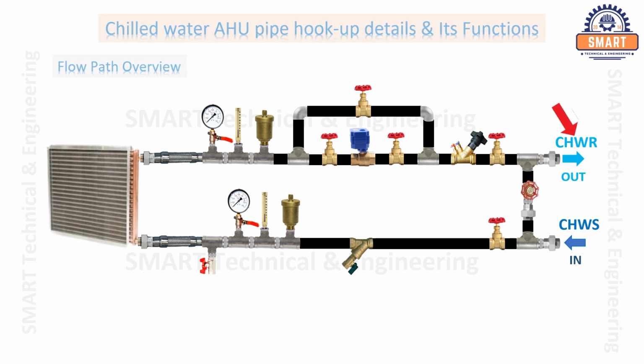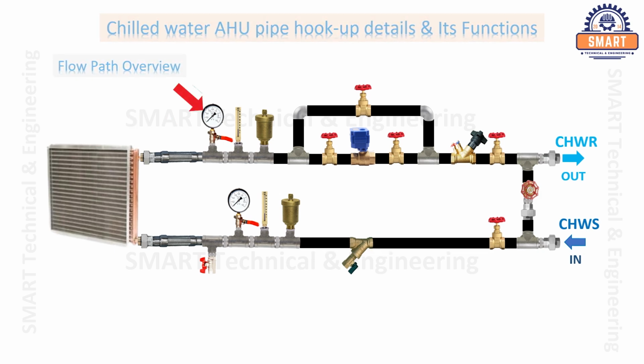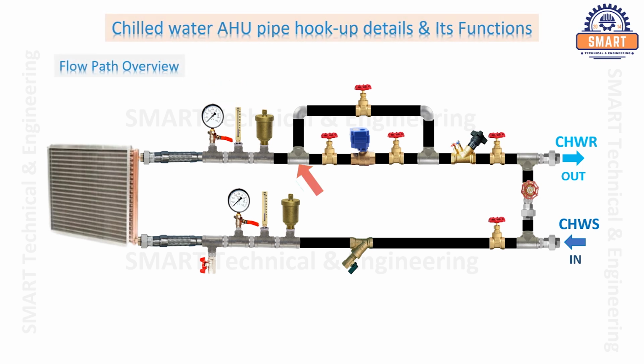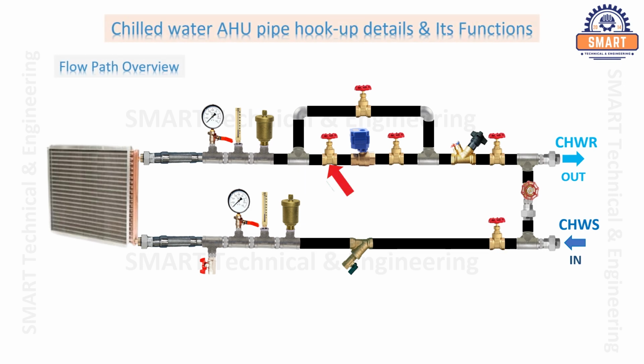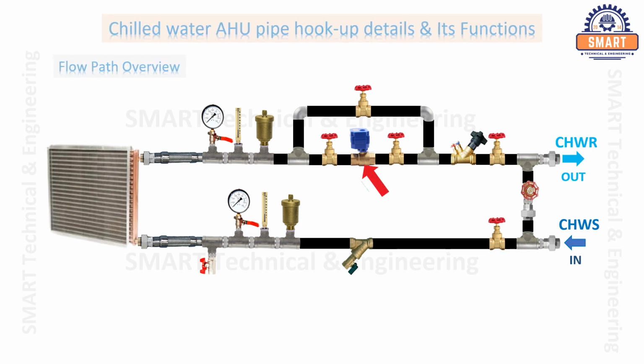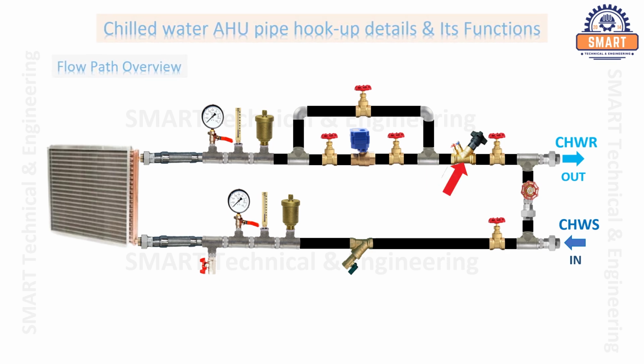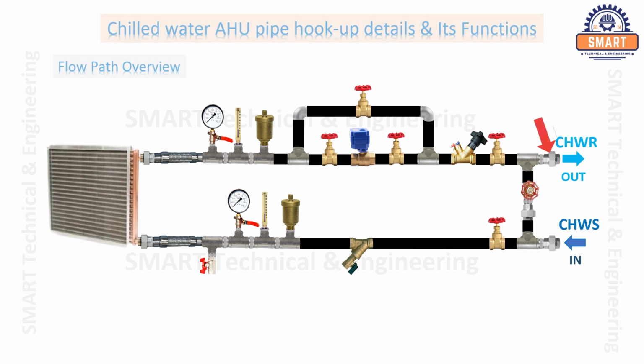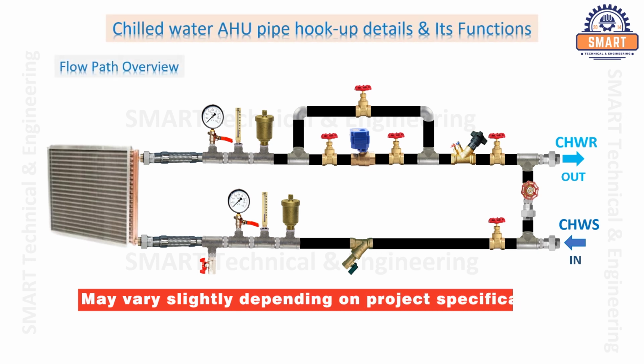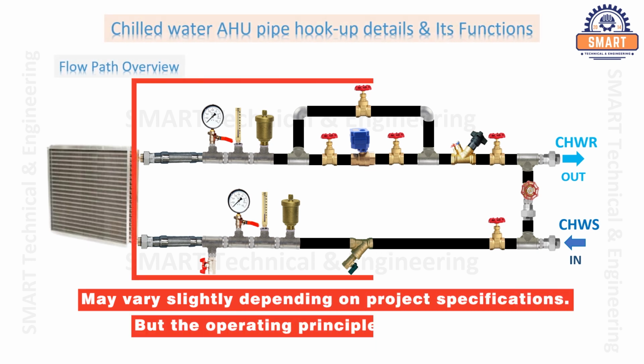For the chilled water return line, leaving from cooling coil, dielectric union, flexible connector, pressure gauge, thermometer, automatic air vent, T for bypass line, isolation valve, two-way motorized valve, isolation valve, T from bypass line, balancing valve, isolation valve, T from bypass line, union to chilled water return pipeline. This arrangement may vary slightly depending on project specifications, but the operating principles remain similar.